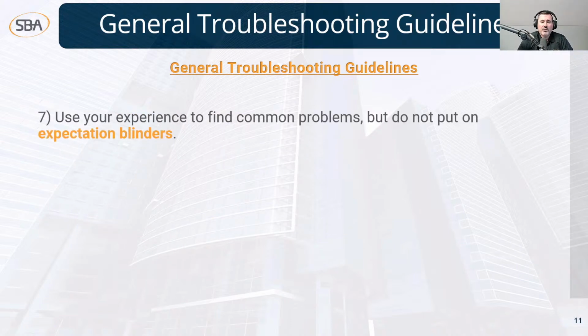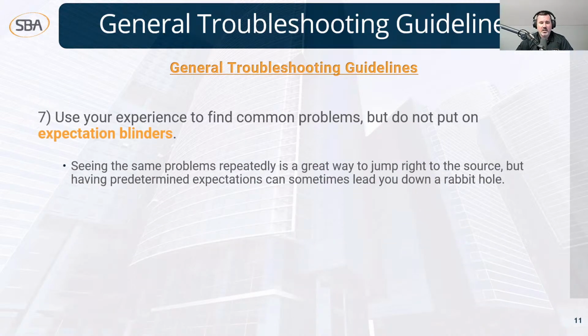Number 7: use your experience to find common problems, but don't put on expectation blinders. Once you've had a lot of time in the field, you start seeing patterns with certain equipment that tends to fail, and this can help you jump right to the source. You might think, these units are notorious for bad blower motors, these ECM motors are always going bad, that's got to be my problem. But don't just go out and start changing the motor. Verify it first, because sometimes we chase a problem that doesn't even exist. It may not be the blower motor at all, it could be the control board or something else not even sending the signal to that motor.